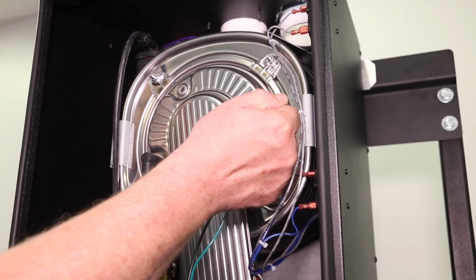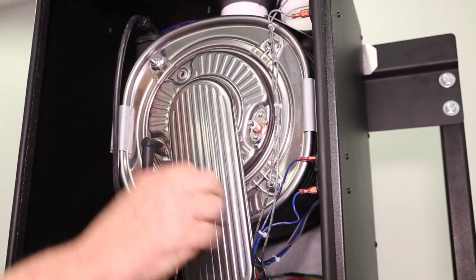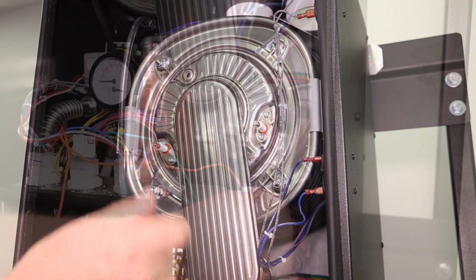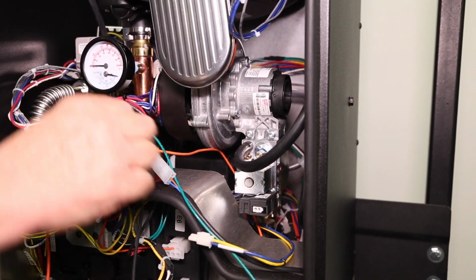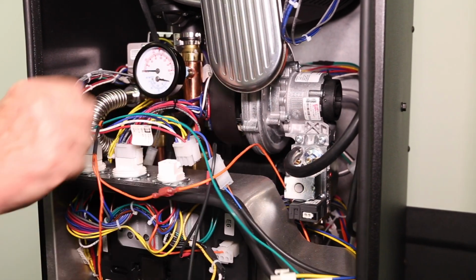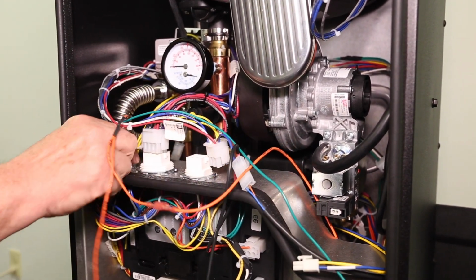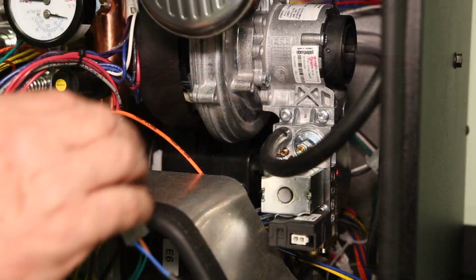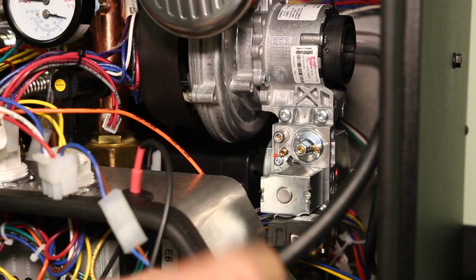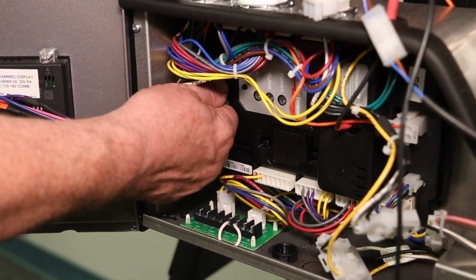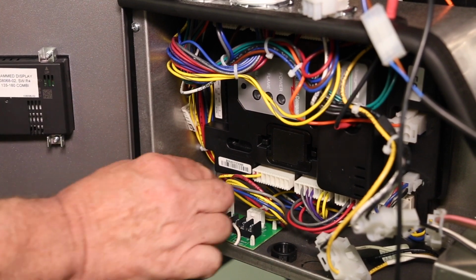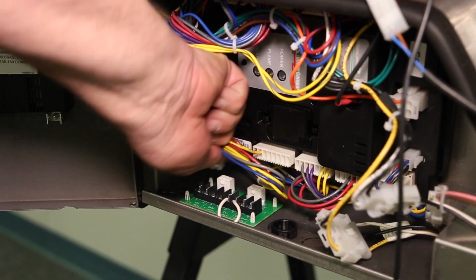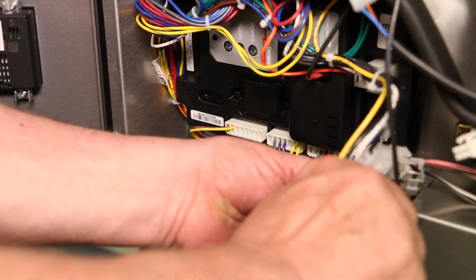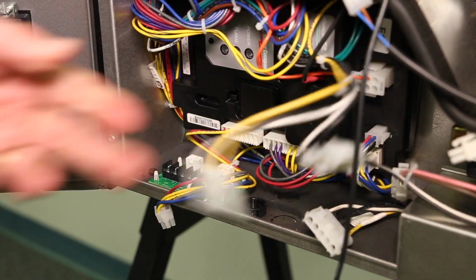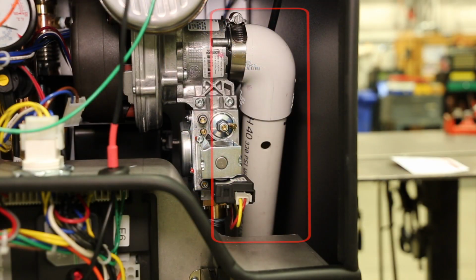First, disconnect the igniter, ground wire, and flame sensor. Then disconnect the wiring harness on the gas valve. Disconnect the 3 wiring harnesses on the top side of the control box. Then disconnect the tube to the air proving switch. Inside the control box, disconnect the display harness, the connection at the printed circuit board, and the power supply connection. If applicable, remove the intake attenuator.